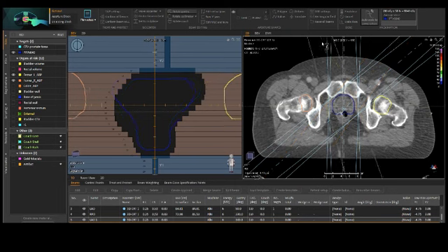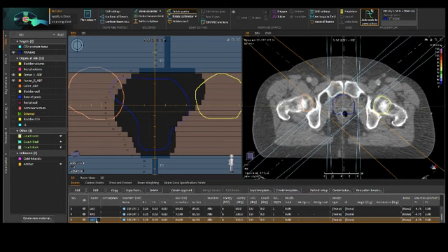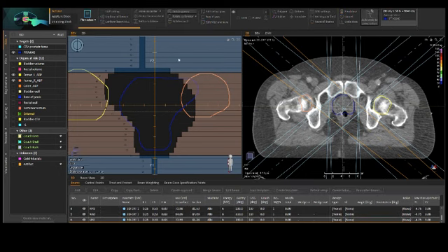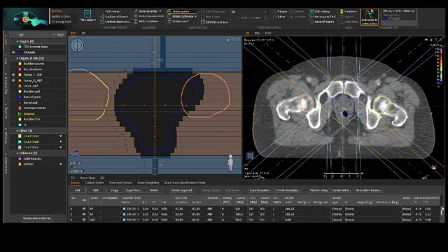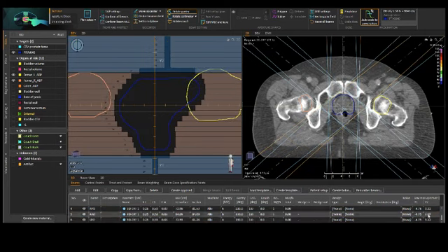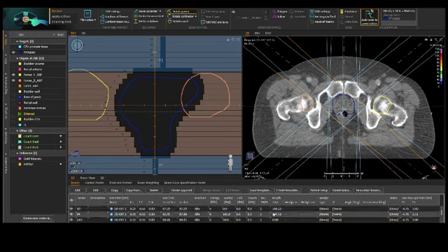So this is the game you play. So you're picking best beam angles, you're conforming the MLCs, maybe you're adding wedges. I'm not going to put any wedges here in this simple example I'm doing. But this is the technique. So then you can conform them. So now they're all wrapping around the PTV. You've got now, 1, 2, 3, 4, 5, 6 beams.